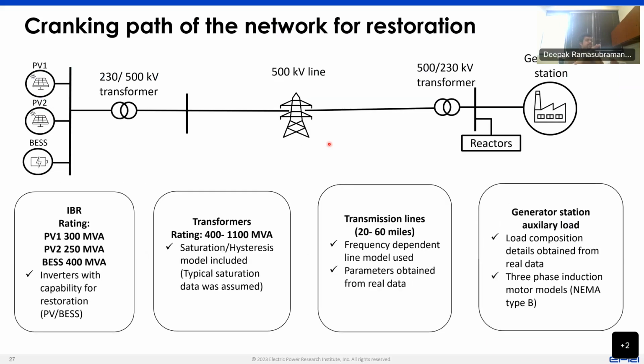So, a very simplistic high-level view of the cranking path. There are more details that we actually study, but at a high level you have a bunch of inverter-based resources connected to a 230 kV transmission point. You have to energize the transformers. You need to energize multiple parallel paths of a transmission line, energize some reactors that are there, pick up motor load, which would be the pumping load for these generating stations, and then bring this generating station online.